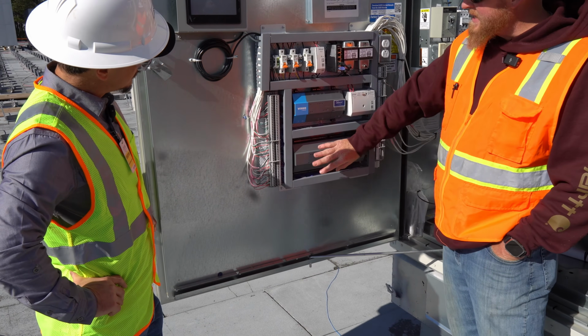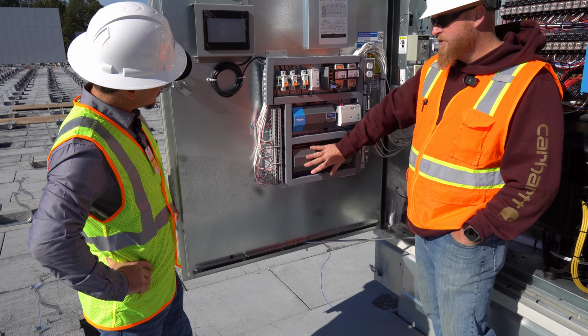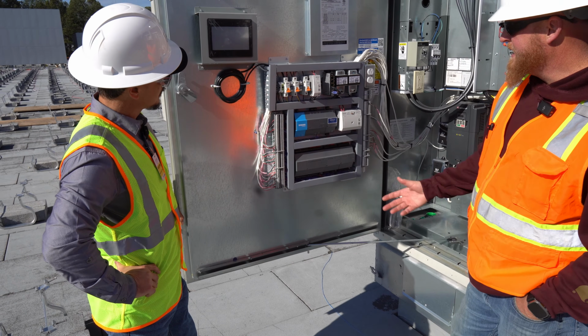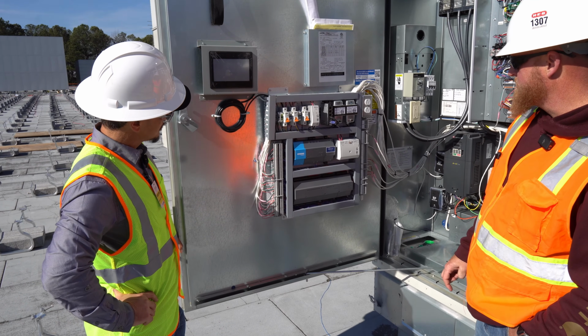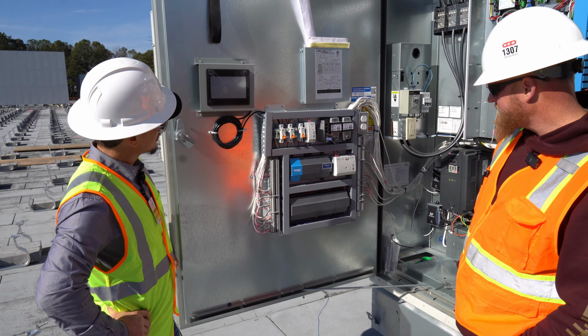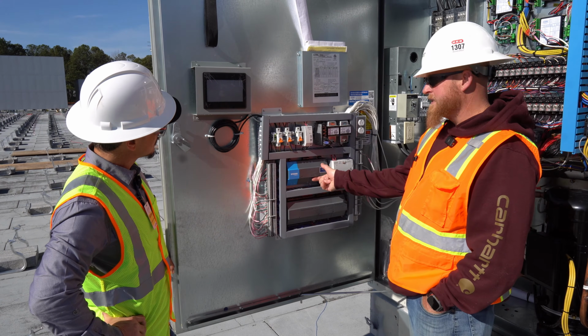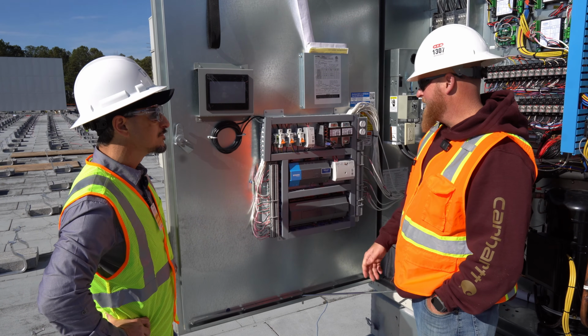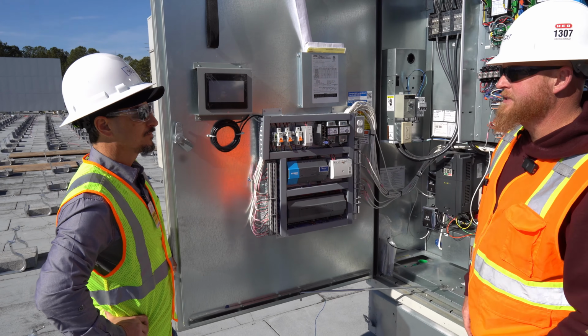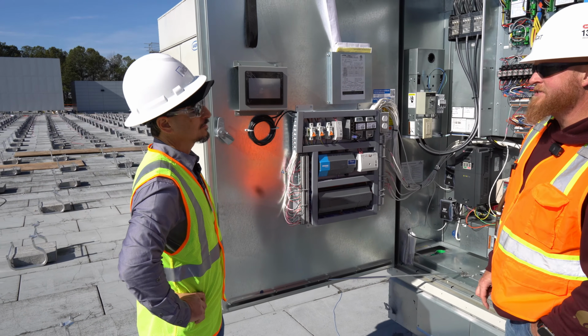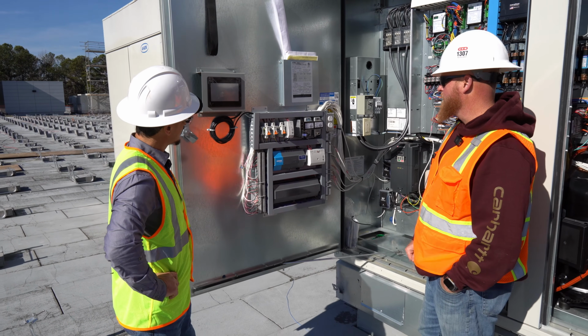We have a 66 IO count, and it's actually fully used on this job, due to the ERU and the number of sensors and data points they want. On this one, we actually had to expand the RS-485, adding additional BACnet communication, just for the number of points and data we were pulling in, so we didn't bog down any networks.